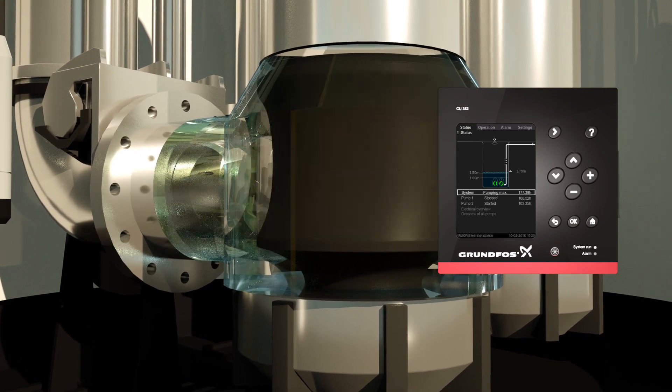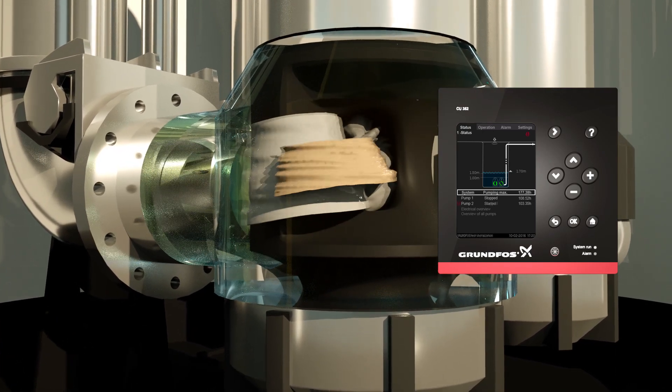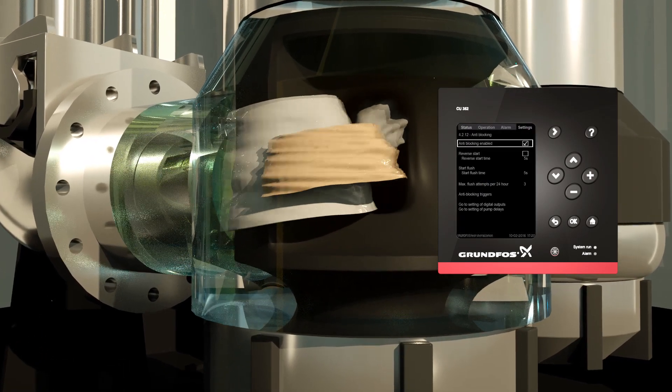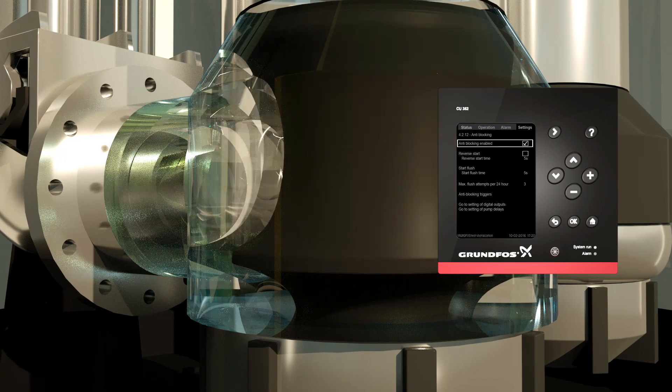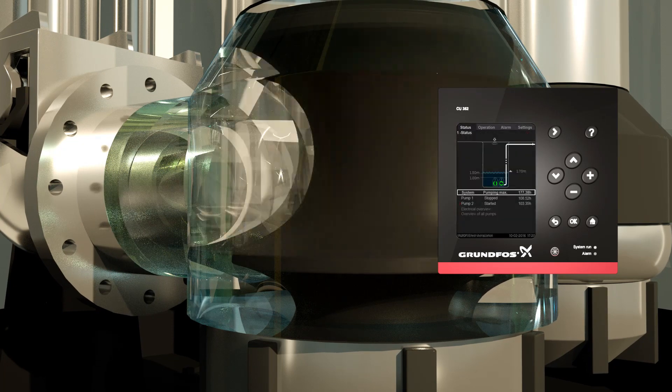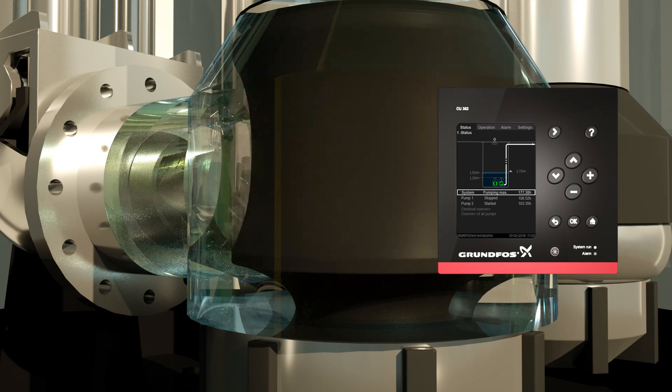However, if a blockage of the pump happens, the controller will recognize this and enable the pump to run in reverse to unblock the impeller. The anti-clogging function acts on any abnormal event, thereby stopping the pumps from blockage, in turn avoiding costly downtime.